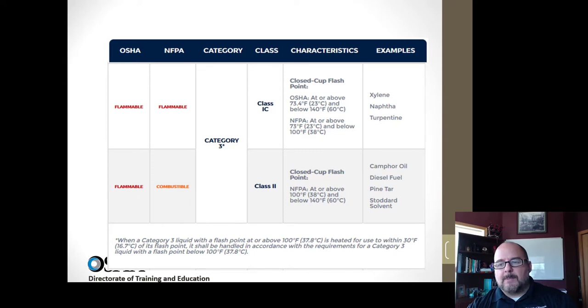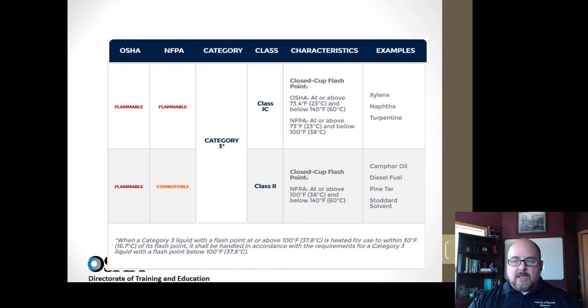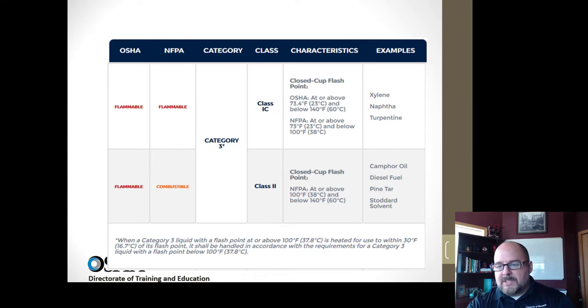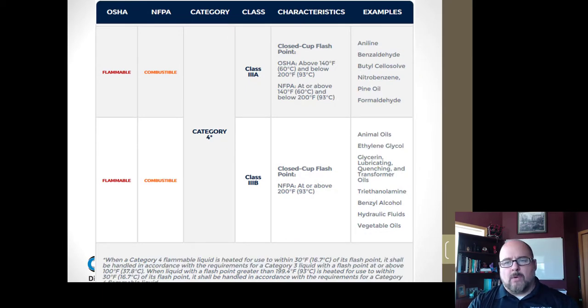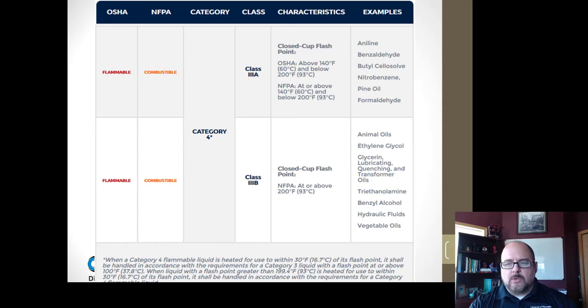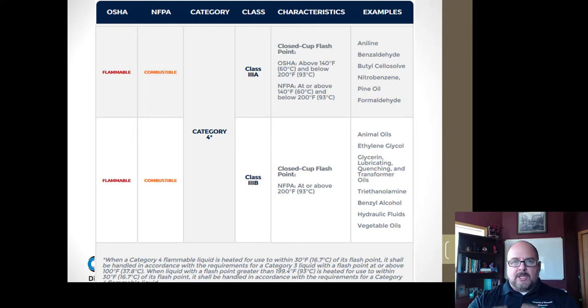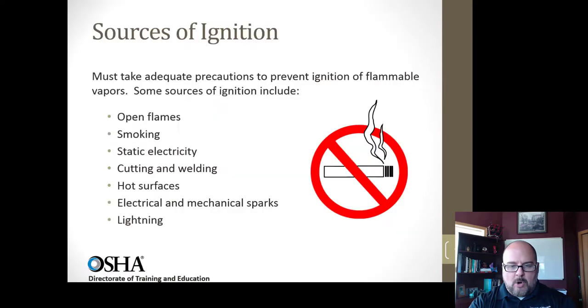Category three liquids typically require either heating or aerosolization to become explosive, but they can burn given an ignitable source — just without the explosive nature of the first two categories, because they don't volatilize as fast. Category three class two gets into diesel fuel, oils, pine tar, and Stoddard solvent, found in parts cleaning solutions. Category four, classes 3A and 3B, would likely take much more to become an explosive cloud and would probably need mechanical means or heating to reach the capability of burning.